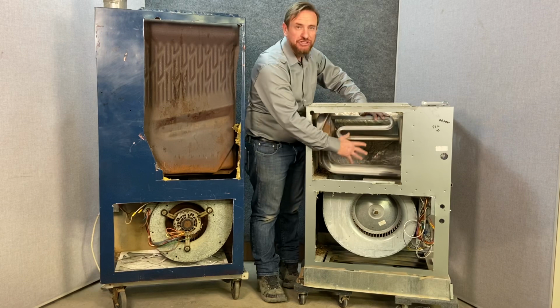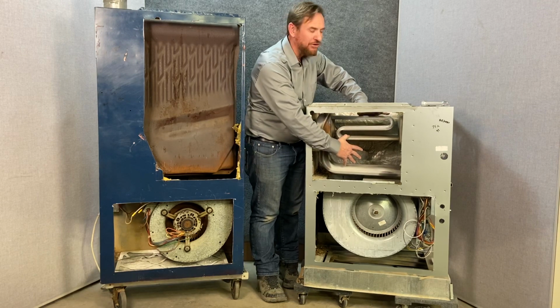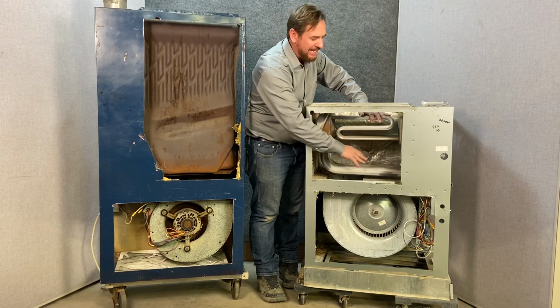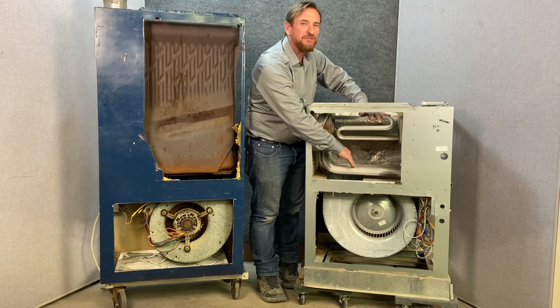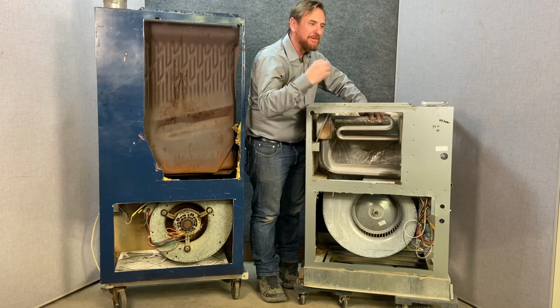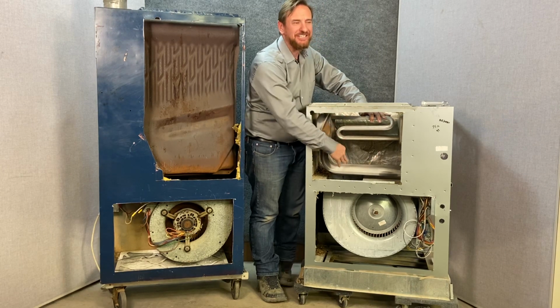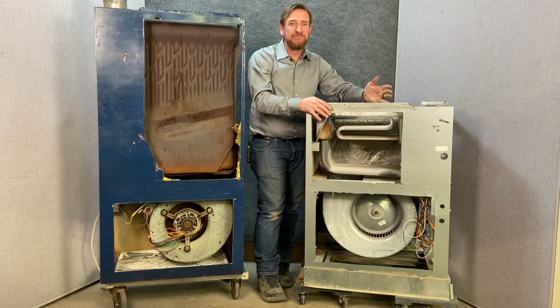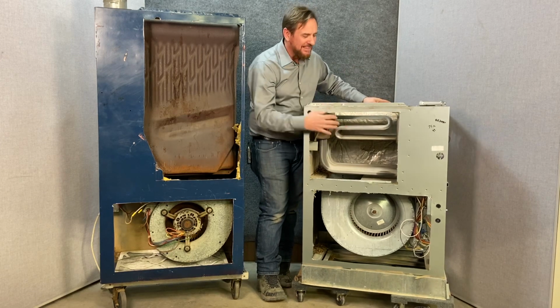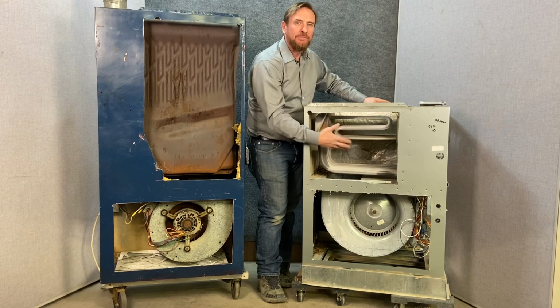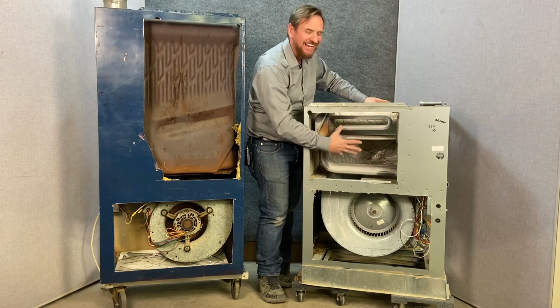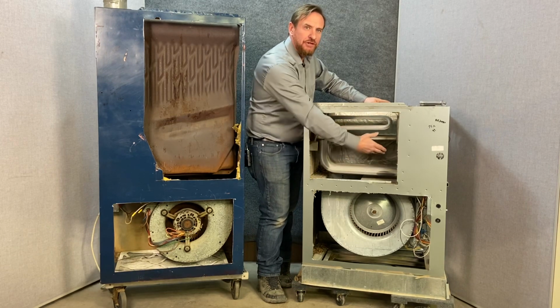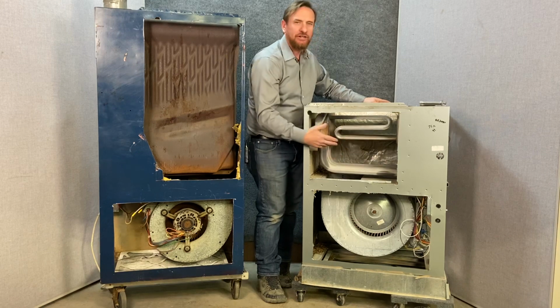So, still an issue. You should never run a unit with a cracked heat exchanger or a hole in it under any conditions. It's just a little safer, in that if you did have a hole in it, it's not going to be an immediate death situation. And I don't like a death situation whether it's immediate or long. So this heat exchanger is a whole lot smaller, a whole lot more efficient. There's tons of different styles of these, but it still works the same. They're shooting the flame horizontally across this.